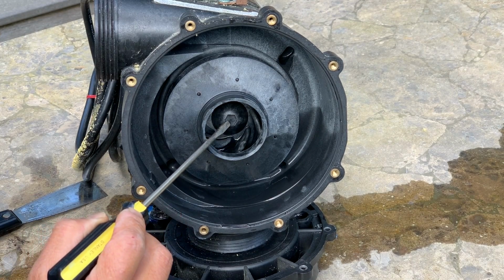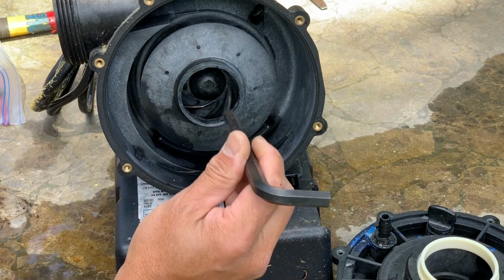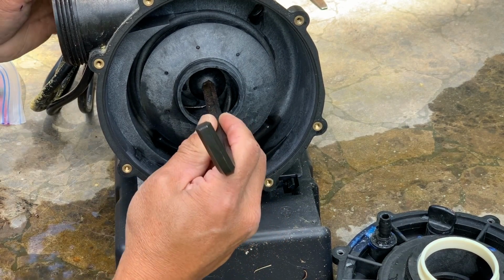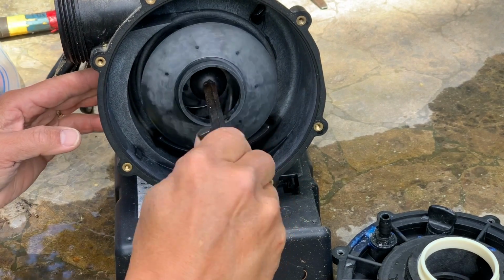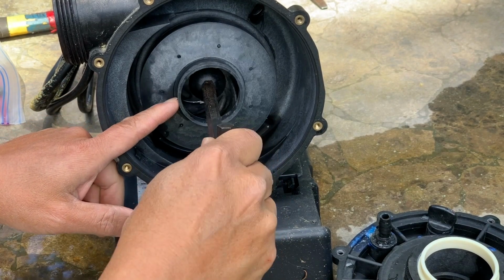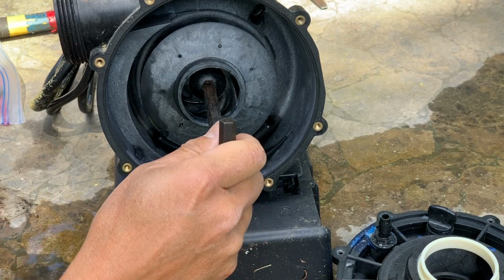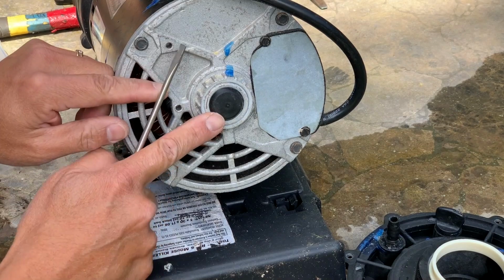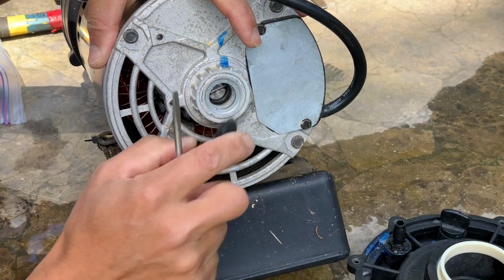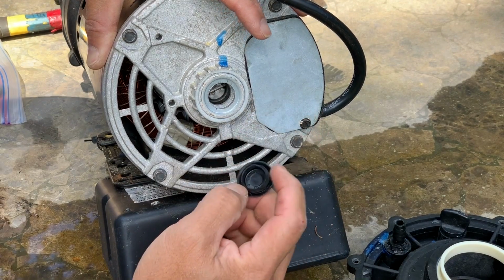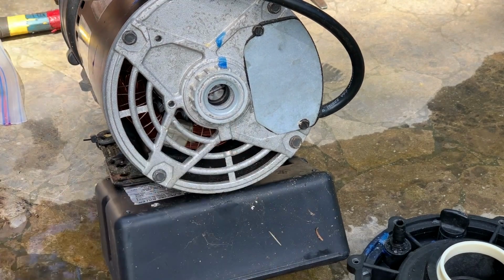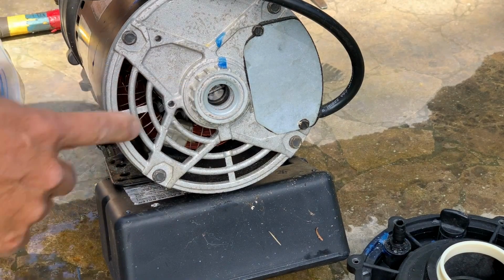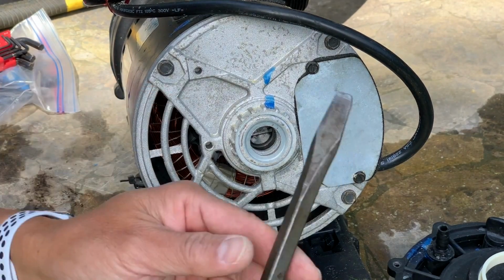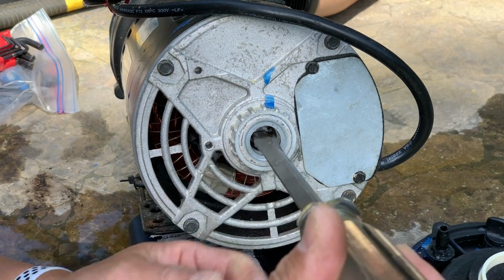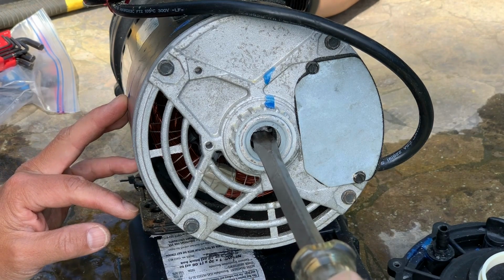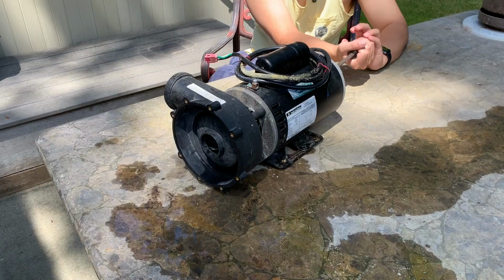It looks like we're going to need a large Allen wrench to loosen this up in the center. Okay, I found that a 3/8 inch Allen wrench does fit into that, but when I turn this, the motor shaft also turns, so we need to find a way to fix the motor shaft and prevent it from turning so we can loosen this. There's a plastic cap on the motor end here, and we just need to pry this cap off. And inside, you can see that there's a slot in the end of the drive shaft of the electric motor. So we'll need to take a large flat-bladed screwdriver to hold the drive shaft in place while we loosen the other end. This will probably require a 2-person operation.